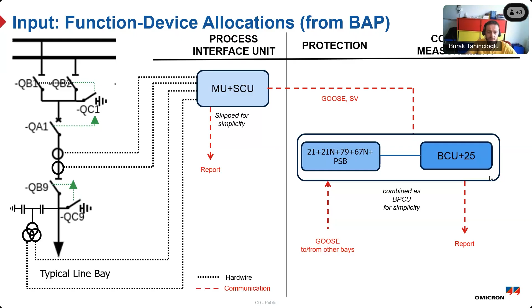And these boxes here, we combine them as one box, and then we will skip the merging unit and SCU also. So we'll have the ANSI code functions here, the distance, you can see some auto recloser, some overcurrent or directional earth fault, and then power swing blocking. And then also we will have some bay controller functions here, another IED maybe, and we will have this specification created by a tool. And another IED that we will also create for specification is the bus coupler.